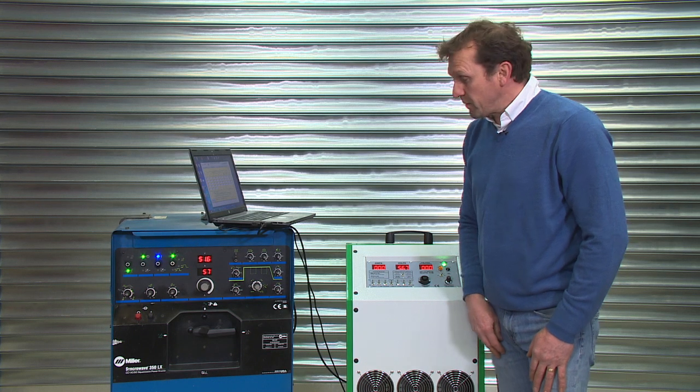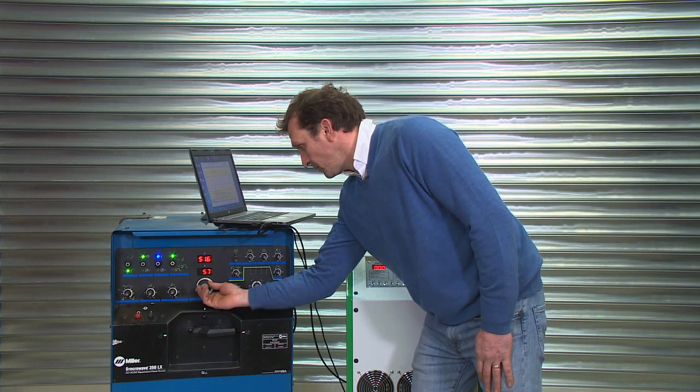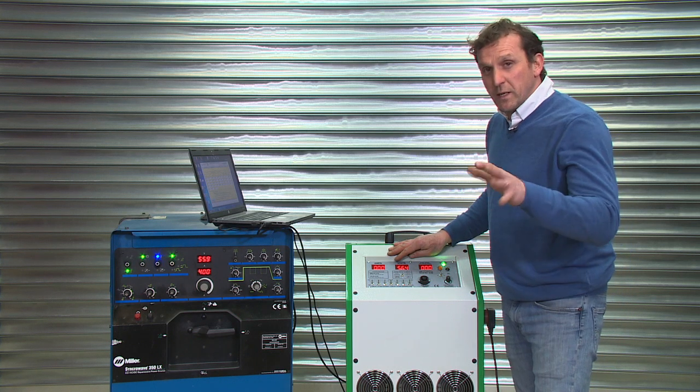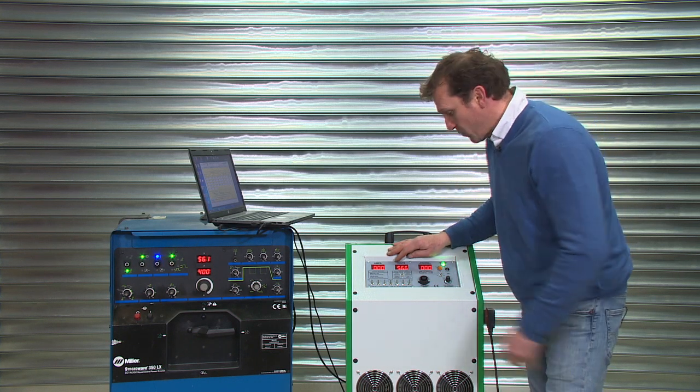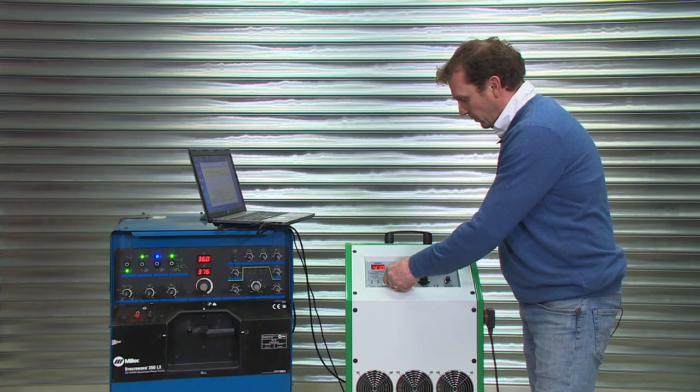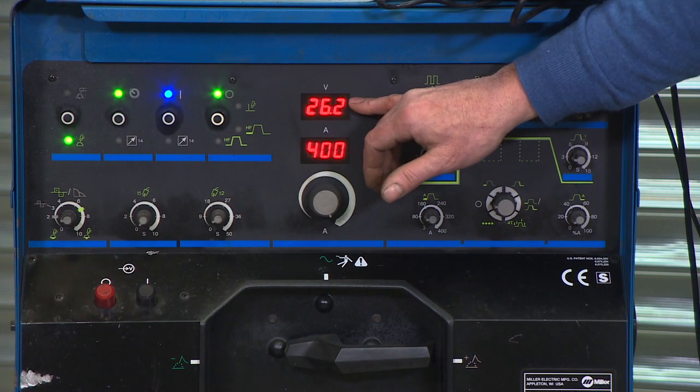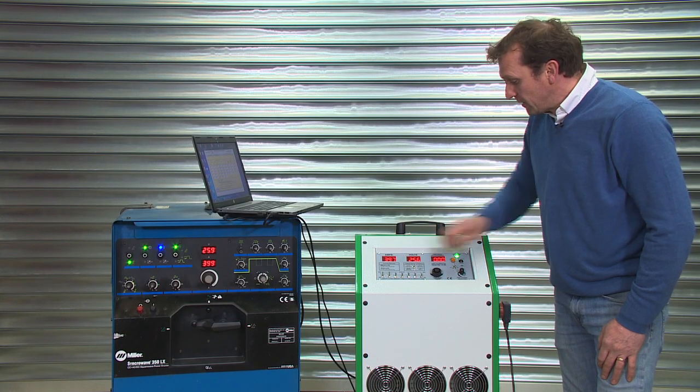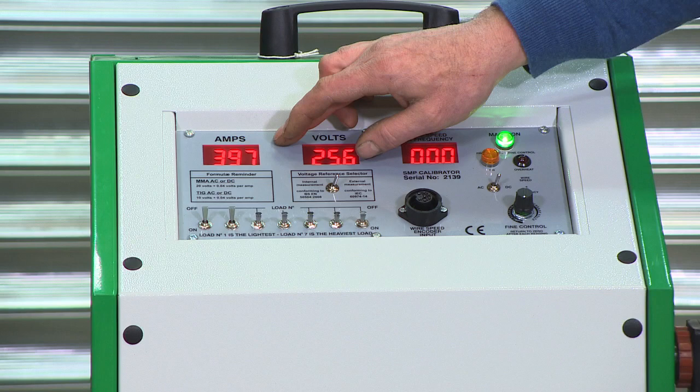Then our final reading, maximum 400 amps. Looking for the voltage of 26 volts within that 10% window. We record 400 amps, 26.2. And the calibrator reading of 397, 25.6.